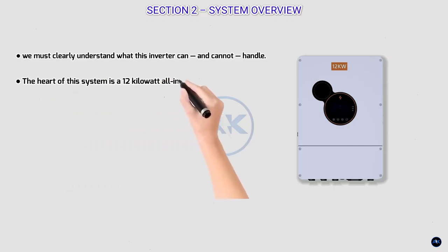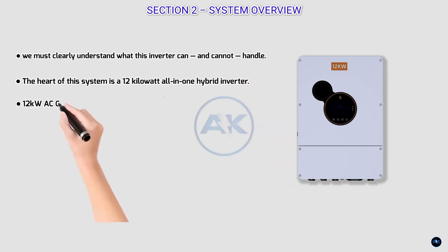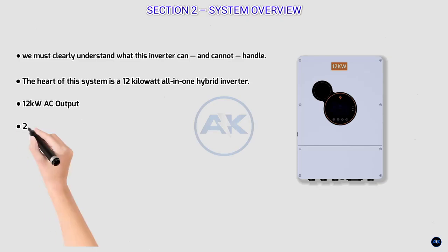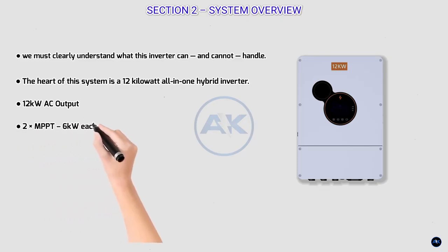Before we connect a single solar panel, we must clearly understand what this inverter can and cannot handle. The heart of this system is a 12 kilowatt all-in-one hybrid inverter. That means the maximum AC output power is 12,000 watts, no matter how many solar panels you connect. This inverter has two independent MPPTs, and each MPPT can handle up to 6 kilowatts of solar input. That's important because each MPPT tracks its own string of panels, and they must stay within very strict electrical limits.